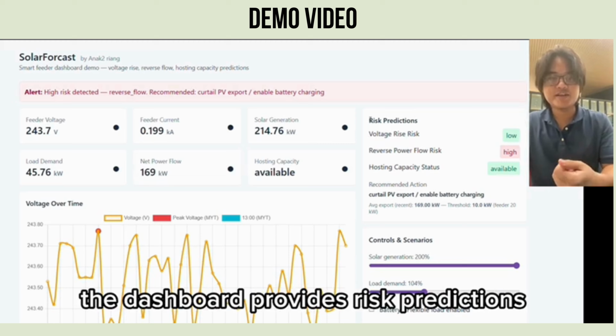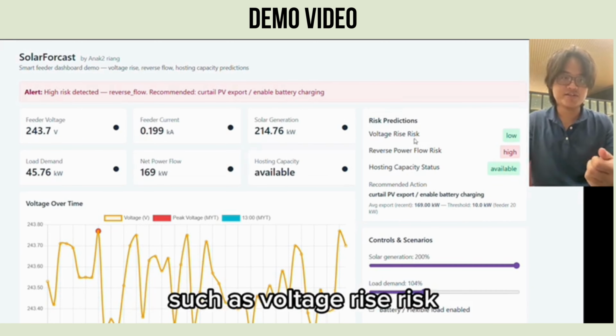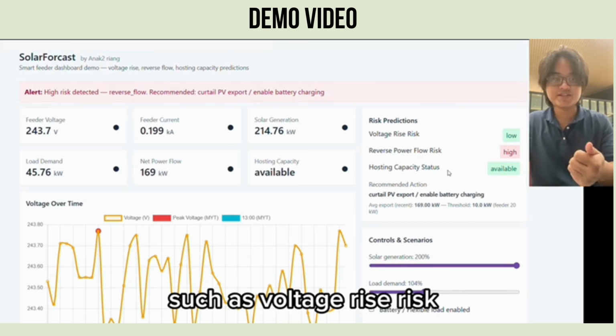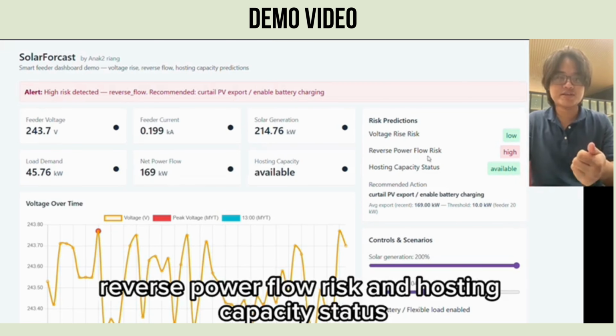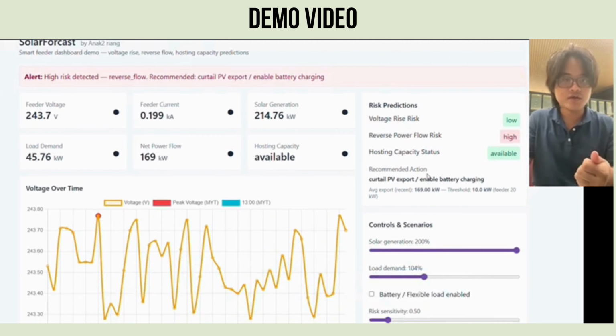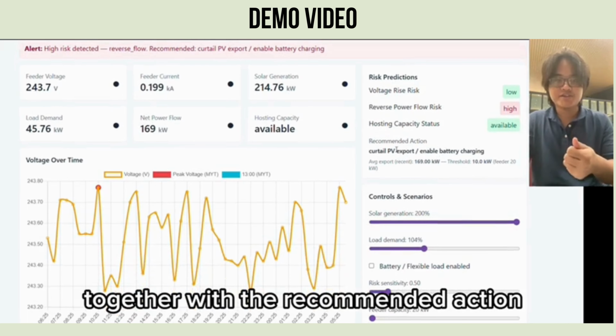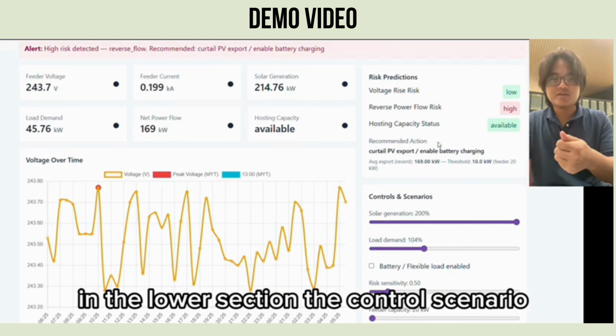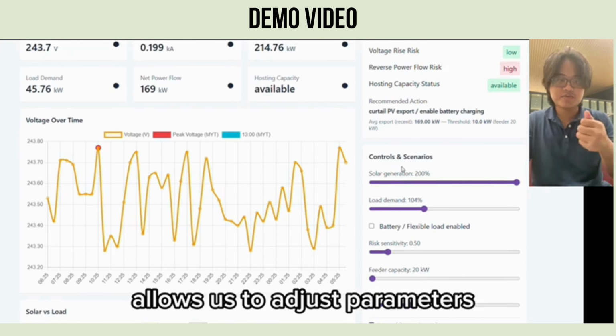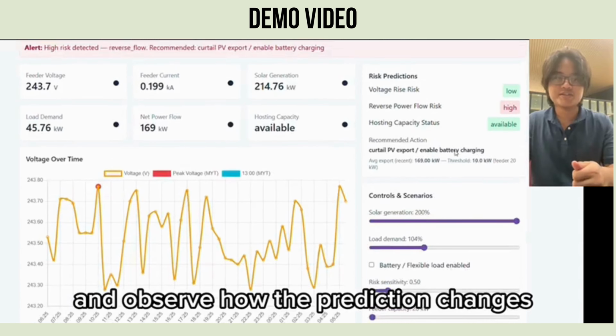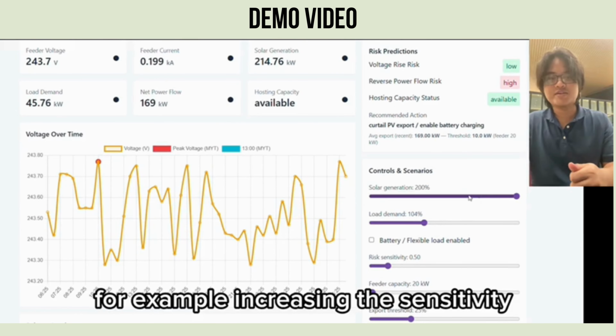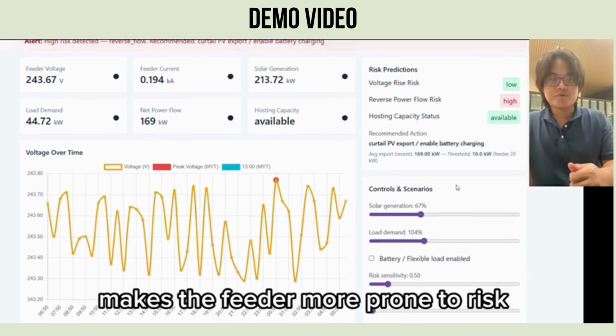On the right side, the dashboard provides risk predictions such as voltage rise risk, reverse power flow risk, and hosting capacity status, together with recommended actions. In the lower section, the control scenario allows us to adjust parameters and observe how the prediction changes. For example, increasing the sensitivity makes the feeder more prone to risk.